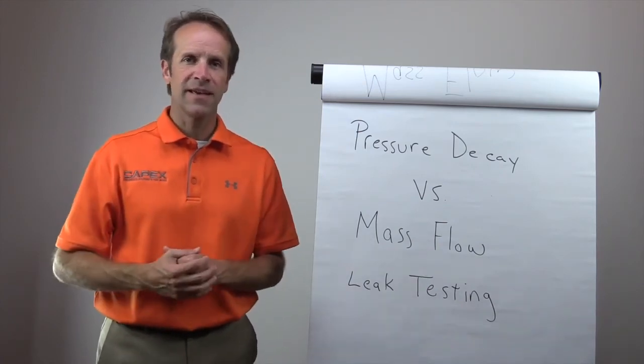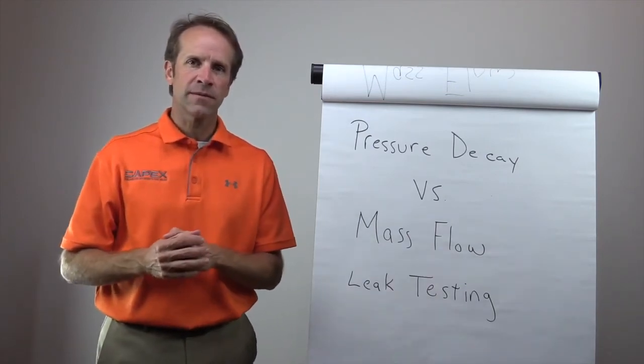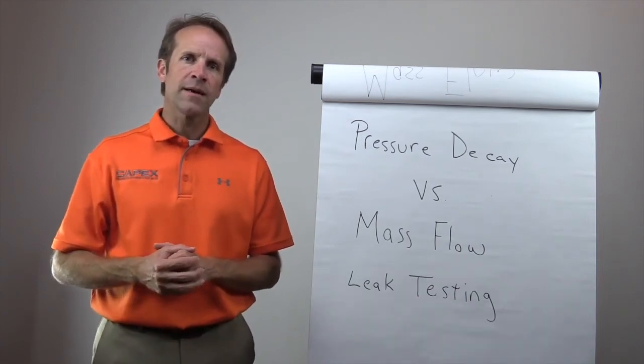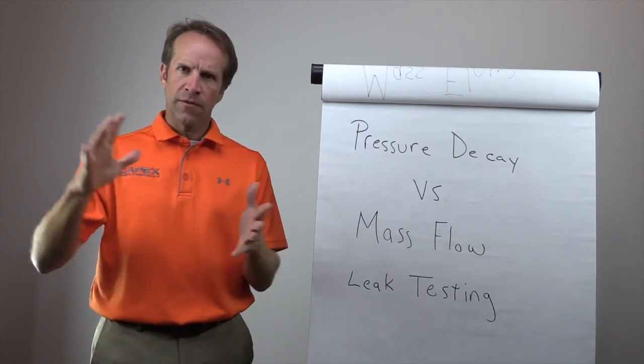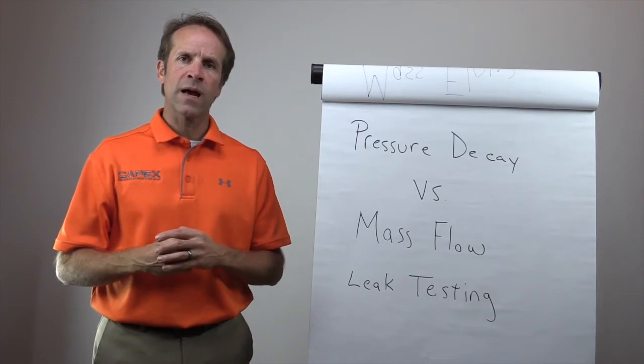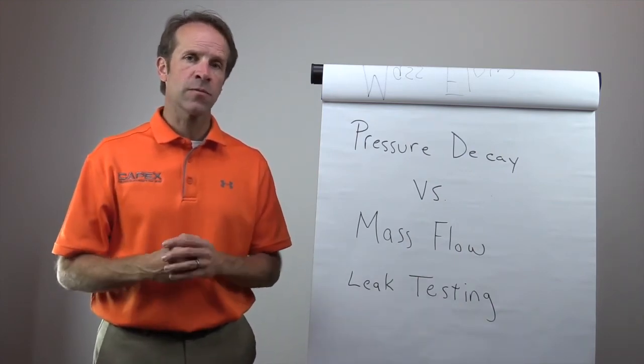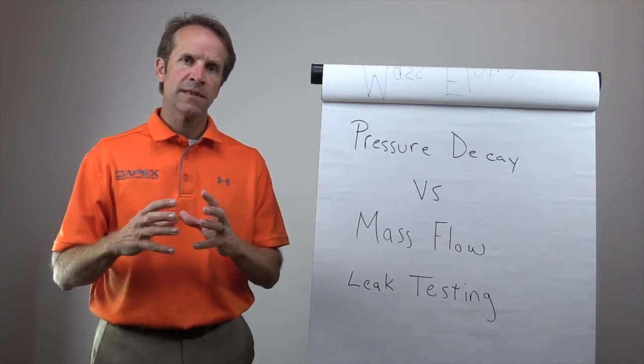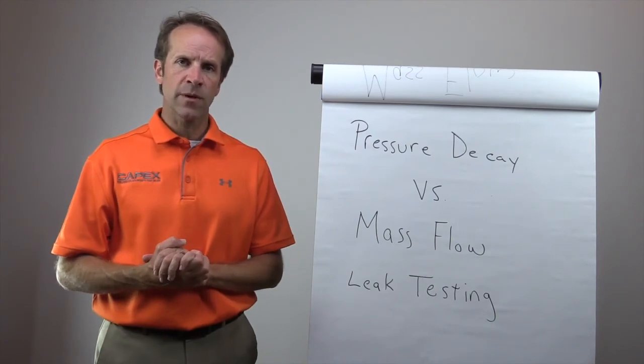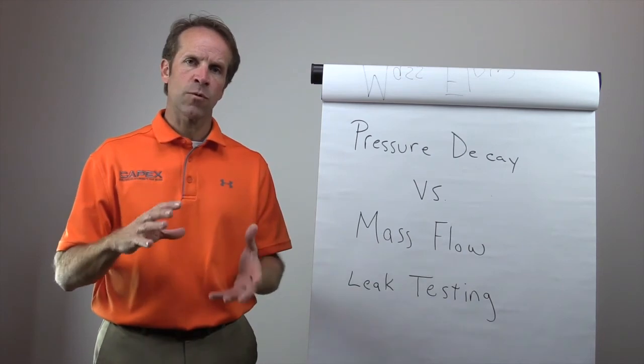You know, you talk to different salespeople, they'll probably all give you varying degrees of confidence in whatever it is that they're going to recommend. But as a general rule, mass flow, larger parts, flexible parts, and also high variation, because you do not necessarily have to calibrate. Now, of course, you can calibrate mass flow. But I'm just saying from a general perspective, if you have a lot of variation, you don't have to do a calibration for each of the parts. You just have to make sure that your cycle time is long enough to test your largest part.